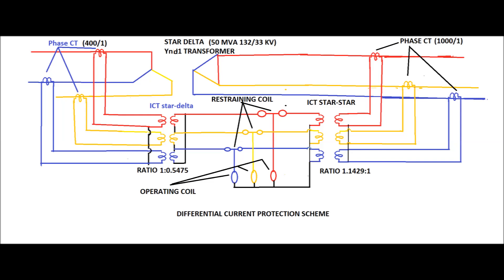The ratio of ICTs on the star-star type ICT is 1 to 1.1429. Restraining coils are used to avoid unwanted tripping or mal-operation of the relay. When the restraining force is less than the operating force, the relay will send a trip signal. This is the principle of operation of the three-phase differential relay.